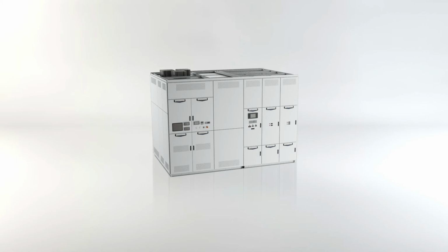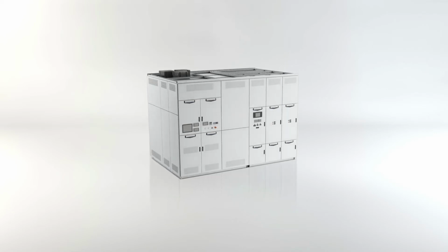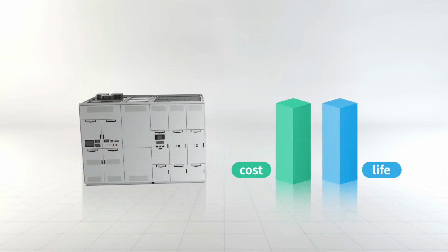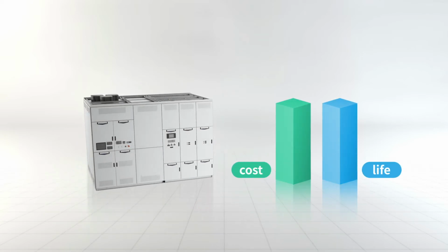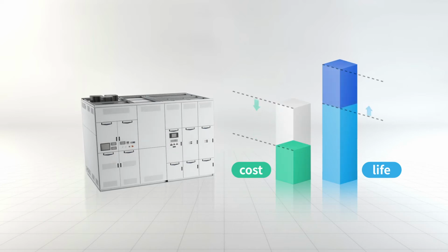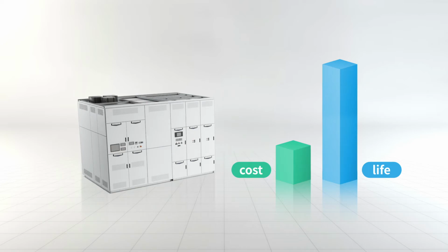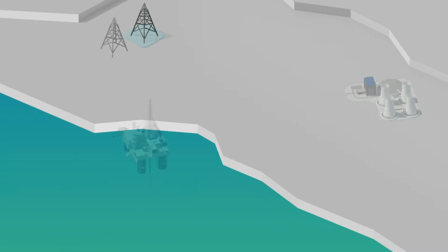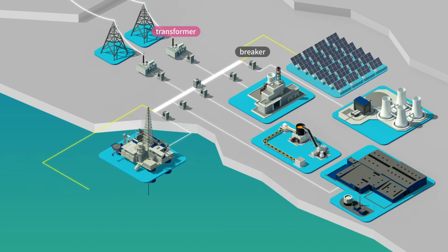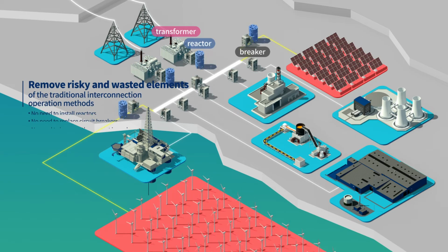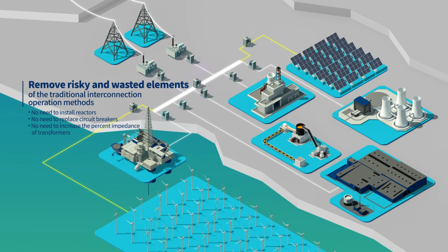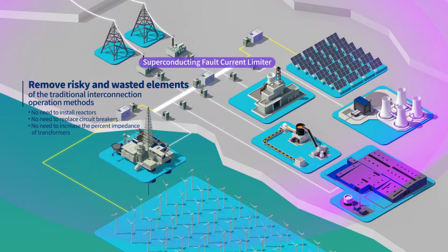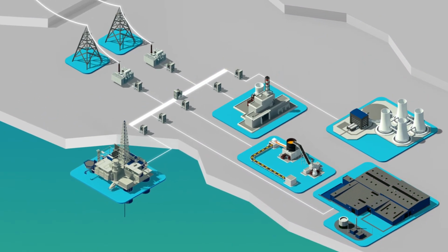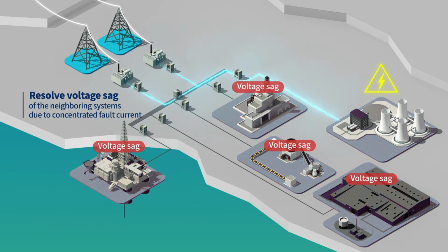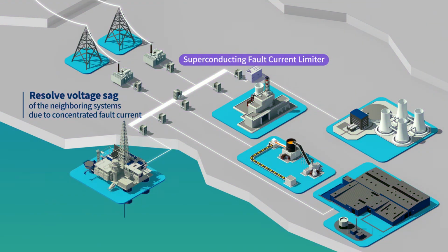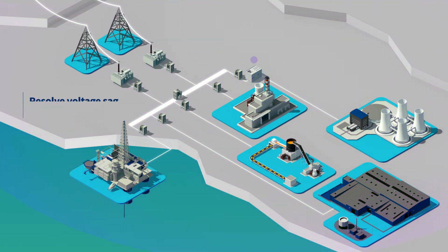Then, what kinds of effects could be enjoyed with SFCL in detail? Thanks to the feature of rapidly reducing major fault currents, the mechanical and thermal stress of electrical devices is reduced, which allows breakage prevention and lifespan extension of electrical power equipment. Most of all, SFCL enables the interconnection operation of electrical power systems in a stable manner by not only perfectly removing risky or wasted elements of the traditional interconnection operation, but also enjoying the whole merits of the interconnection operation. It also resolves problems like voltage sag of the neighboring systems that occurs due to a concentrated fault current, so the power quality is improved.